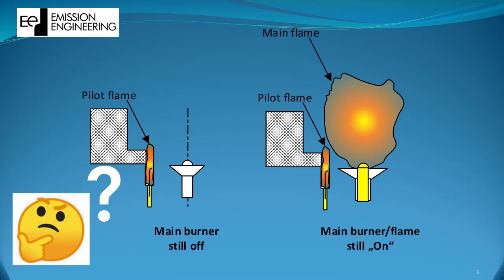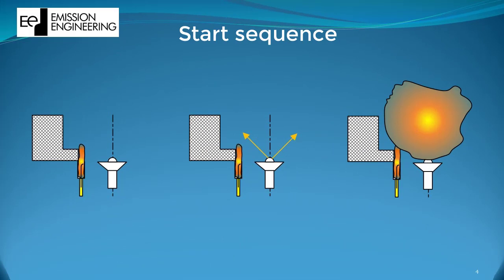The main purpose of the pilot burner is to light the main burner. In order to have a clear start prerequisite for the related main burner, a signal for the PLC is needed. That is the purpose of flame detection via ionization.